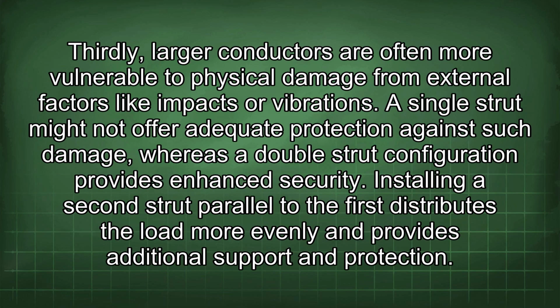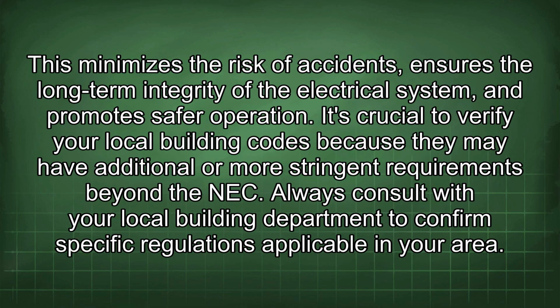Thirdly, larger conductors are often more vulnerable to physical damage from external factors like impacts or vibrations. A single strut might not offer adequate protection against such damage, whereas a double strut configuration provides enhanced security. Installing a second strut parallel to the first distributes the load more evenly and provides additional support and protection. This minimizes the risk of accidents, ensures the long-term integrity of the electrical system, and promotes safer operation.